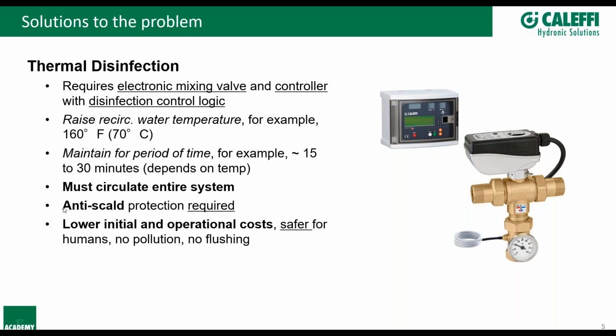Under normal circumstances, our control is not going to be the one telling the recirc system to turn on and off. Under every scenario, I always recommend constant circulation in a domestic hot water recirc system. This goes back to the idea that warm, stagnant water breeds Legionella bacteria - if you keep the water moving, not stagnant, you limit the amount of bacterial growth.